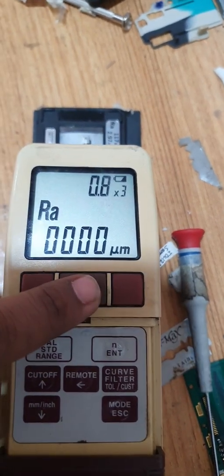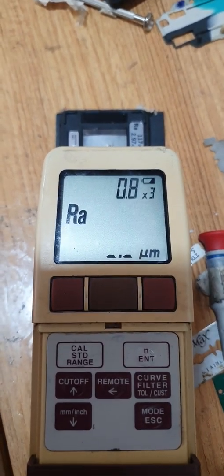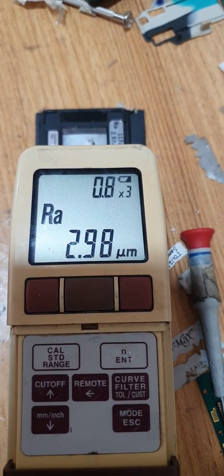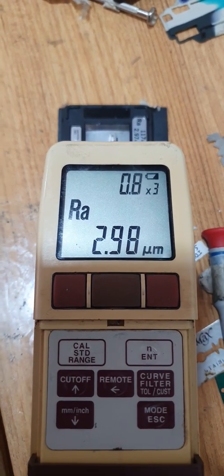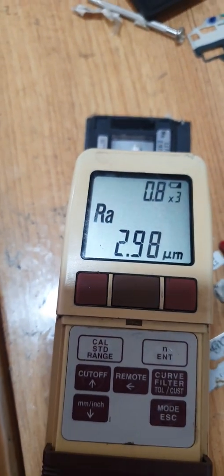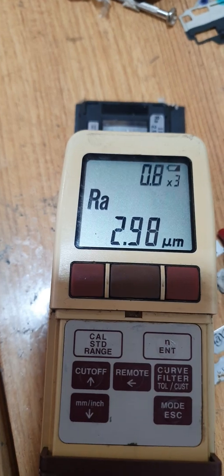Let's check again. Now the reading is 2.98, which is okay. As per the Mitutoyo standards, the accuracy of this master is 3 plus or minus 3 percent of 2.97. If you like this video, please like it and subscribe to my channel.